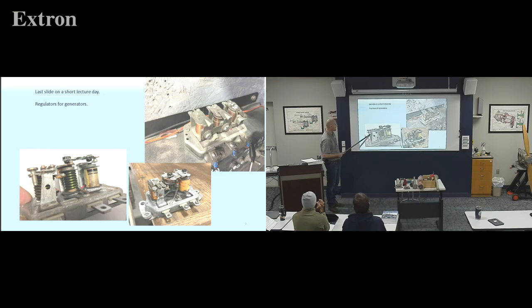The last one on a 3-point is our reverse current cutout. Basically my power goes through this one and then goes through that one. If the power is going the correct direction, this guy will end up getting closed. If the power starts going backwards - you notice when we were testing our generators, if we held him closed or when we flashed the field, we motorize our generator so the current is going backwards through the generator - if the current's going backwards, the magnetic field of this big heavy guy is basically going to open that contact back up.